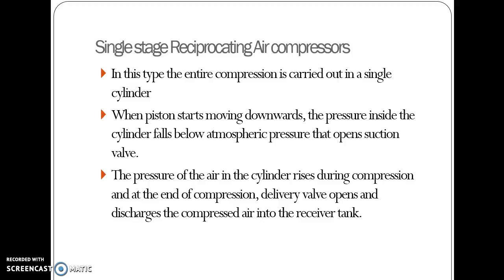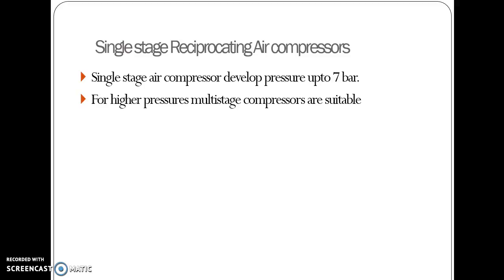There are two types of reciprocating air compressors: single stage and double stage. In the single stage reciprocating air compressor, the entire compression is carried out in a single cylinder. When the piston moves downward, pressure inside the cylinder falls below atmospheric pressure, opening the suction valve. During compression, the delivery valve opens and discharges the compressed air into the reservoir tank. A single stage reciprocating compressor develops pressure up to only 7 bars; for higher pressure, we need multi-stage compression.